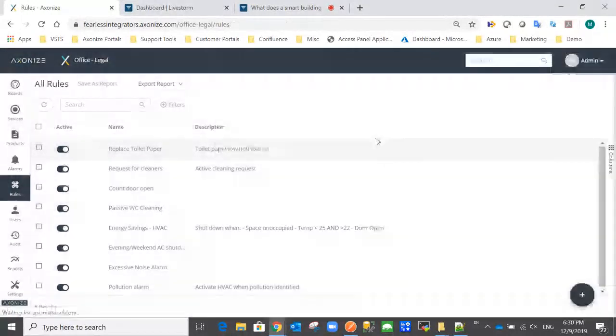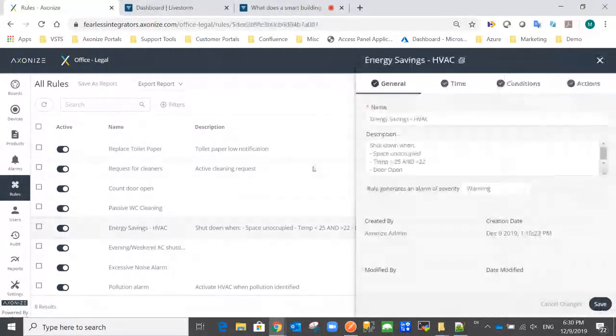A more interesting rule we have here is saving energy. I want the air conditioning to shut down when the space is unoccupied, when there's no one in the office to enjoy the cooling or heating, when the temperature is outside the range between 22 and 25, and when the door is open, because an open door just wastes energy.